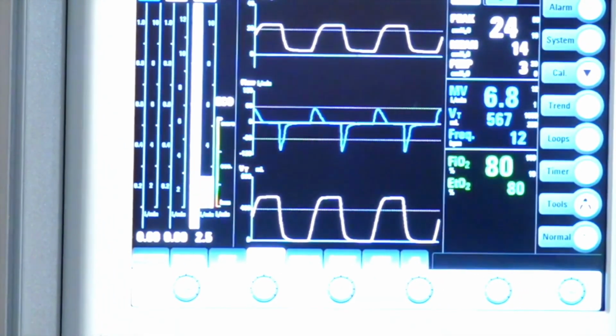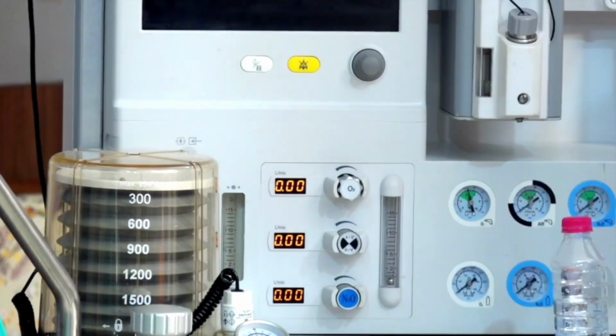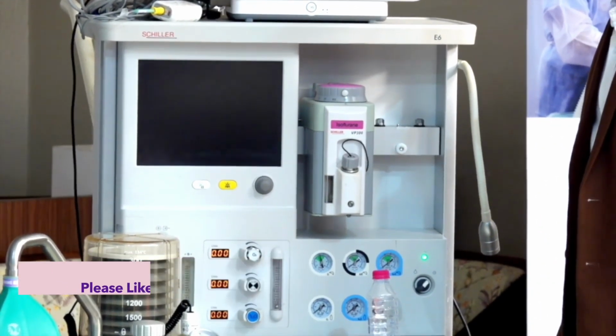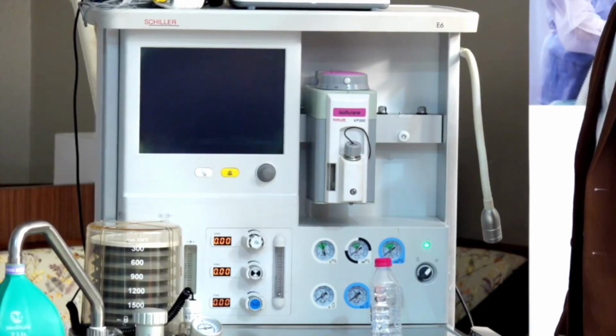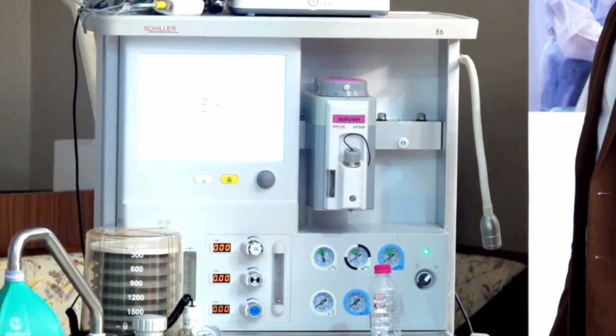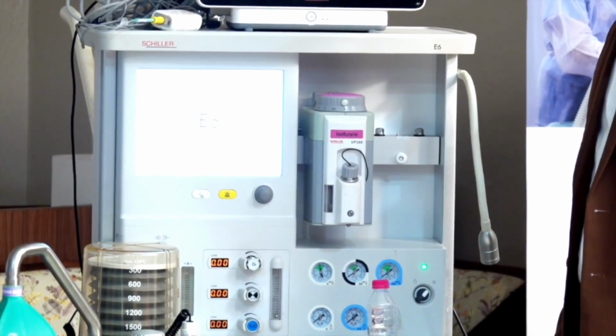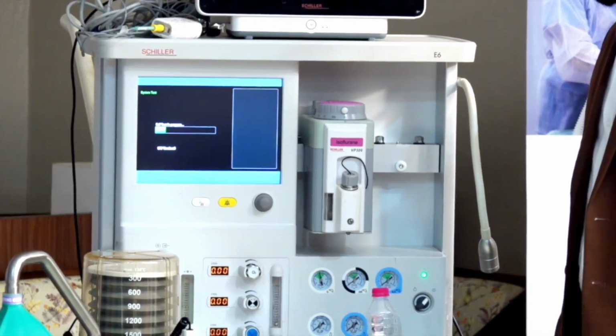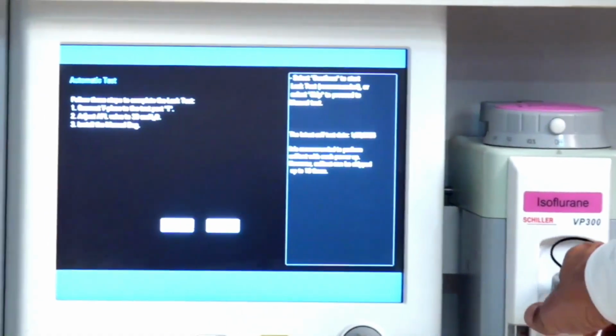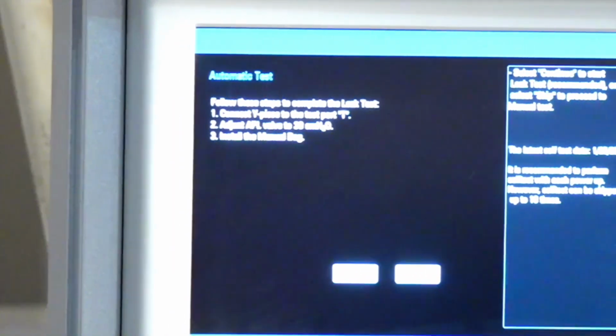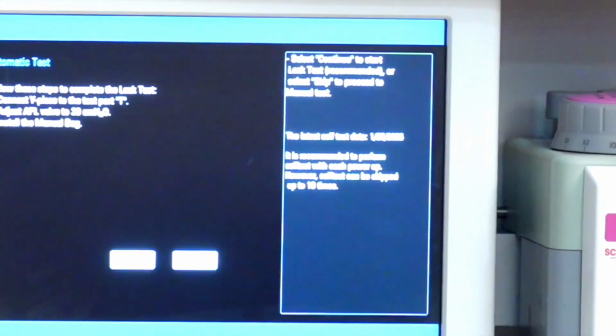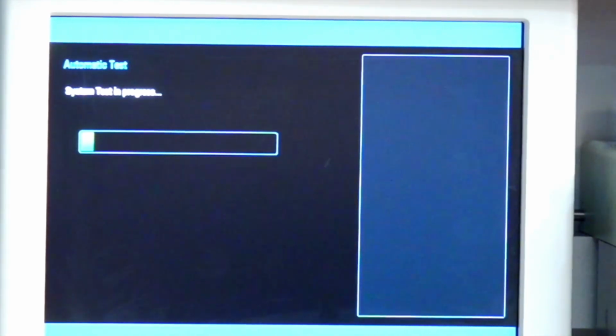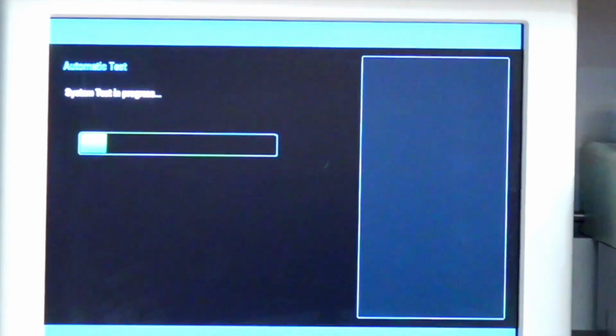Can you show the test data, self-test? Every time you are checking, the self-test will actually take you through that entire process, including vaporizer check. But if it is not there, in that two-bag test which we have discussed, you should also open the vaporizer and check, when you are using it with the ventilator, whether there is any particular leak, because very commonly we tend to forget this, we keep it closed, and there is a leak. So you should also open the vaporizer while the ventilator is working in the two-bag test. So basically it will test everything, leak, compliance, and it will give us the information.